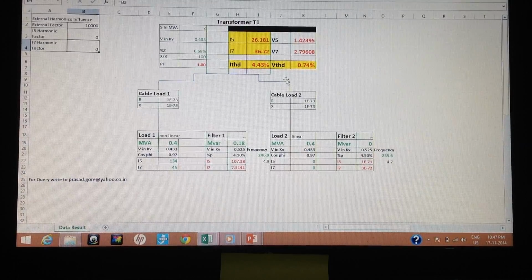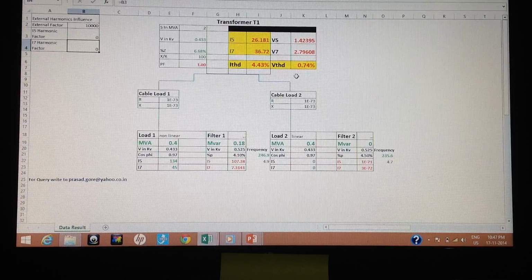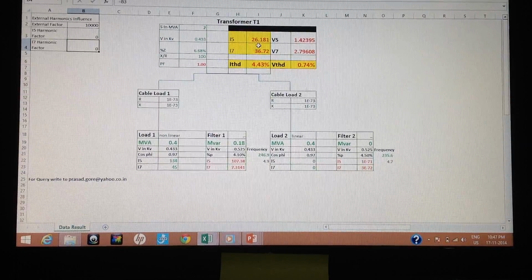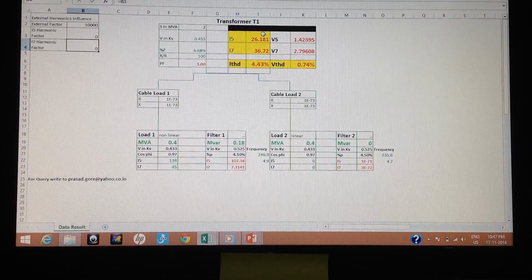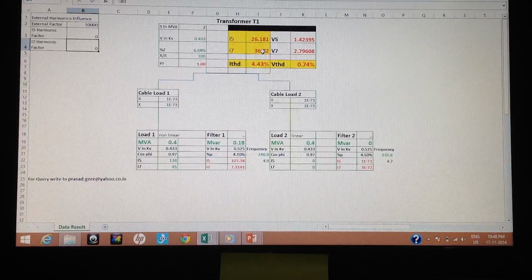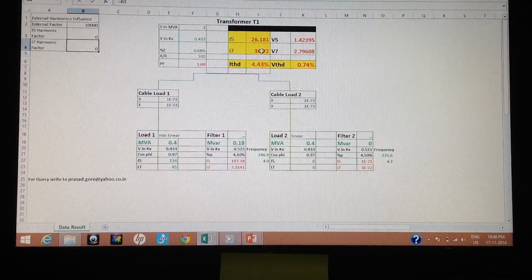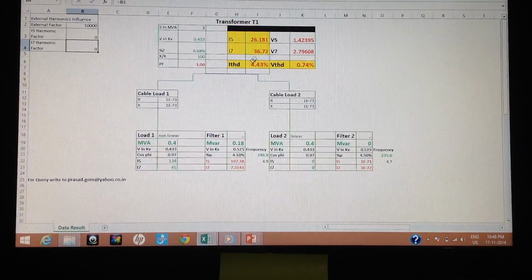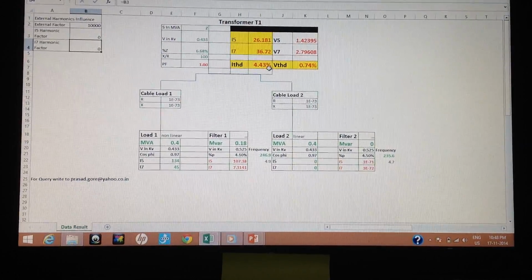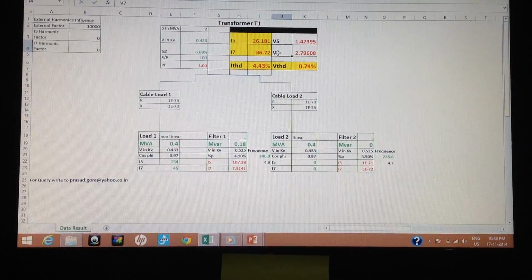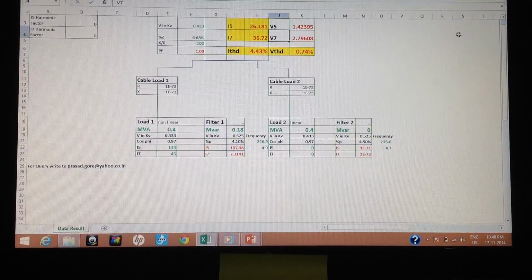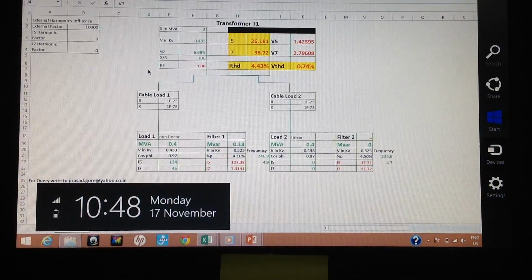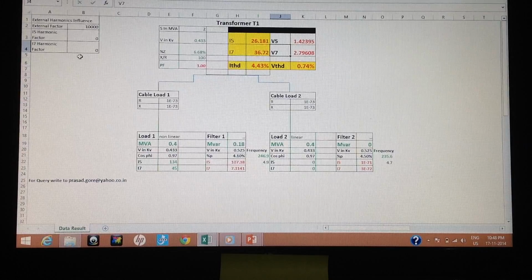So you can see, when there was a 7% filter, we were achieving 116 here and 40 here, but having 246 Hertz series frequency, we are achieving 26 and 36. So it's a tremendous achievement. But if this is done overlooking the external factors, this filter will not perform the way it is performing in this scenario.